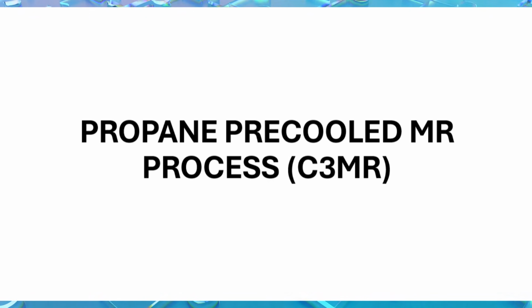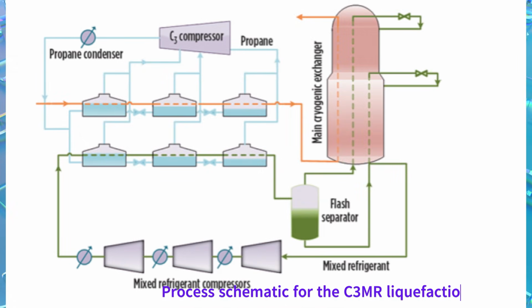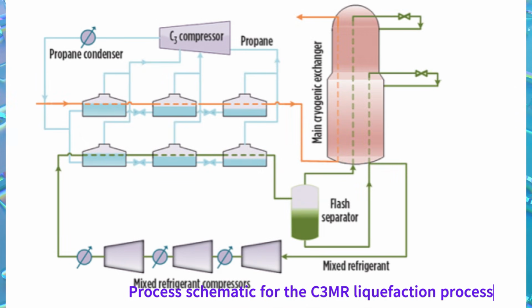The C3 mixed refrigerant process involves a pre-cooling cycle that uses a single-component refrigerant, propane, and a liquefaction subcooling cycle operated with a mixed refrigerant. A process flow diagram is shown. During the pre-cooling stage, the refrigeration cycle is applied in multi-stages at different pressures to cool both the gas stream and the warm MR to approximately -35 degrees Celsius.